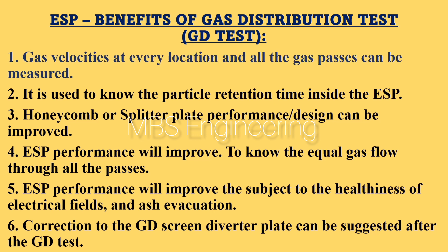Benefits of the gas distribution (GD) test: Point 1: gas velocities at every location and in all gas passes can be measured. Point 2: it is used to know the particle retention time inside the ESP. Point 3: honeycomb or splitter plate performance design can be improved. Point 4: ESP performance will improve by knowing the equal gas flow through all the passes.